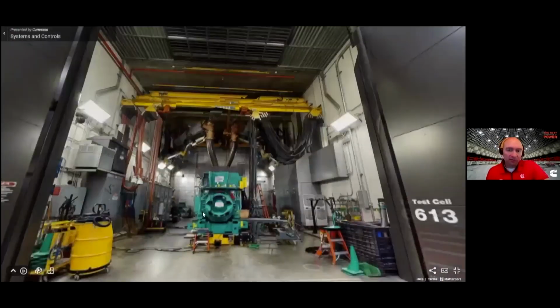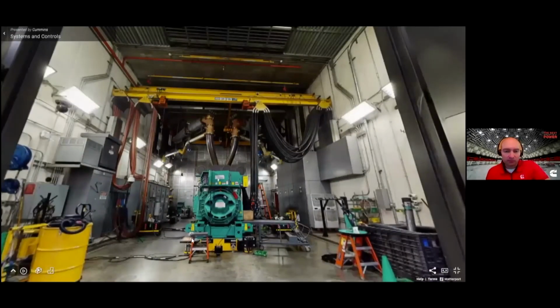Right now there's a 95-liter genset installed in the space. You can see our different load bank cables here to accommodate our different voltage range. We've got flexible exhaust with a joystick control for alignment coming from the roof. We can do mounted radiator or units with no radiator, achieved through large 6-inch diameter flexible rubber hoses coupled to the water pumps on the engine, circulating water through heat exchangers outside.